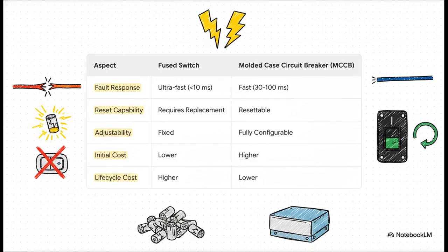With an MCCB, an engineer can go in and completely configure its trip curve, telling it exactly how and when to react. A fuse, it is what it is. It's fixed. It perfectly sums up the choice: raw, blazing fast but dumb speed versus smart, adjustable, reusable control.